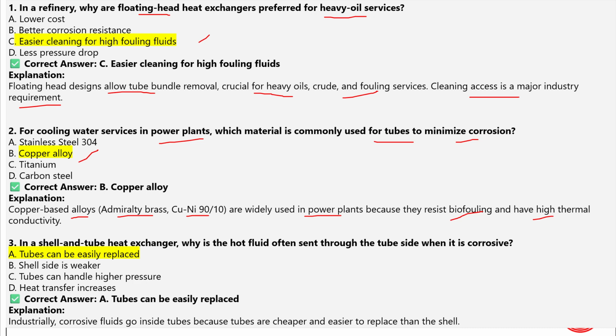Next is, in a shell and tube heat exchanger, why is the hot fluid often sent through the tube side when it is corrosive? So the correct answer is tubes can be easily replaced. Industrial corrosive fluids go inside the tubes, because tubes are cheaper and easier to replace than the shell. It's not easy to replace the shell, but it's very easy to replace the tubes. That's why the corrosive hot fluid is often sent through the tubes.